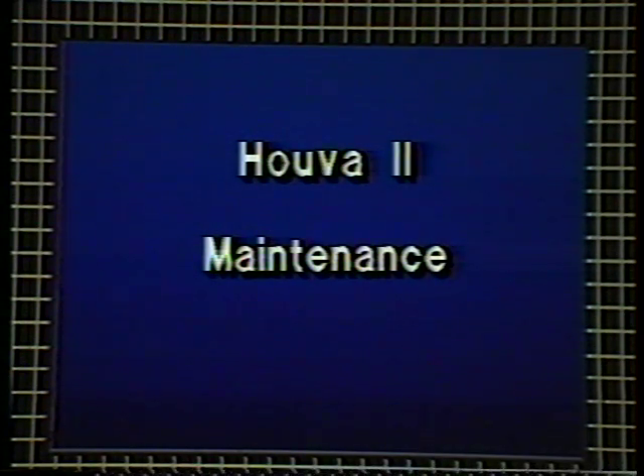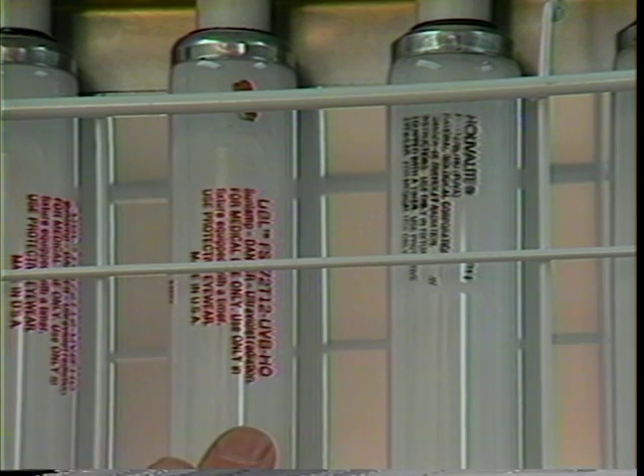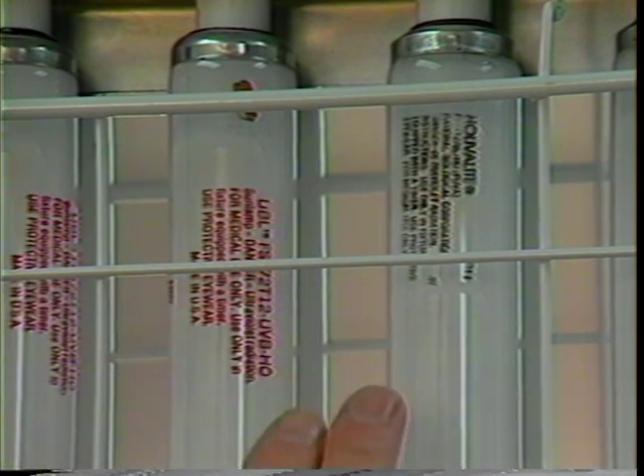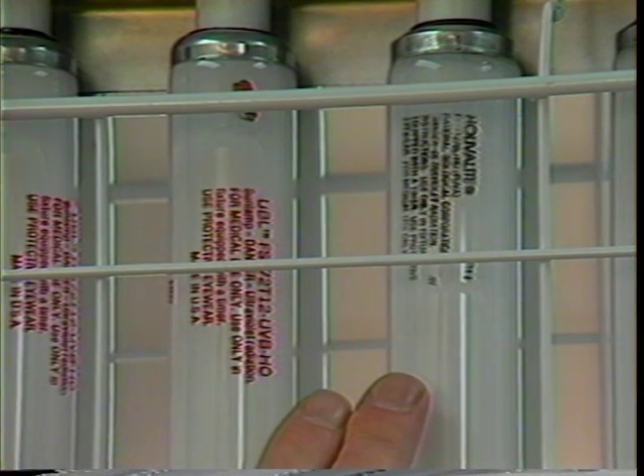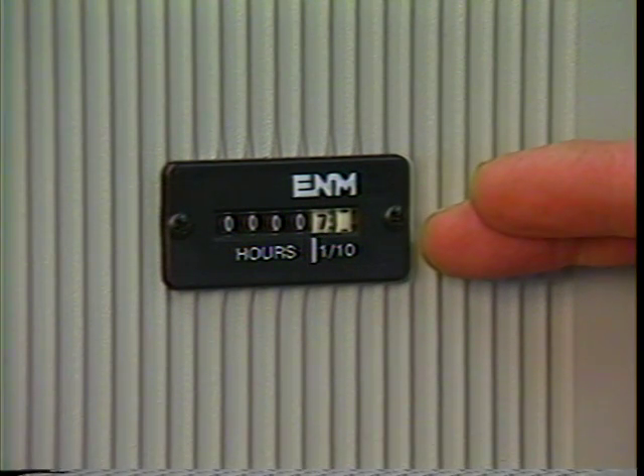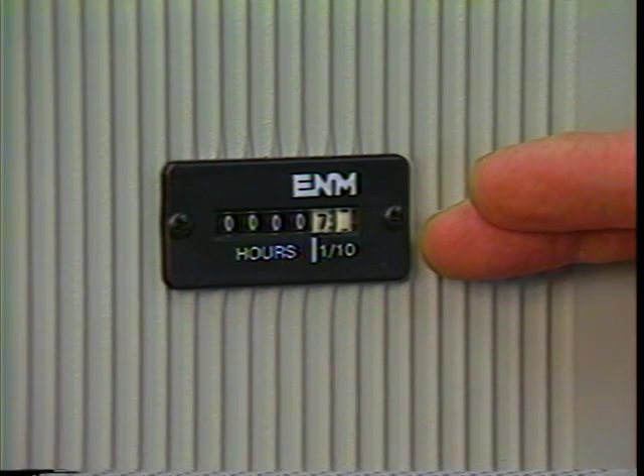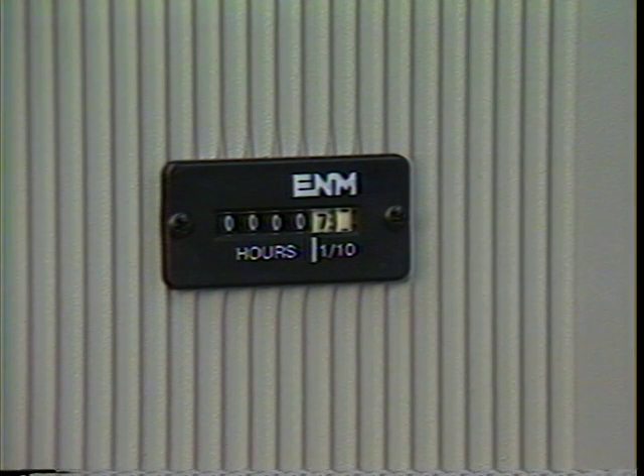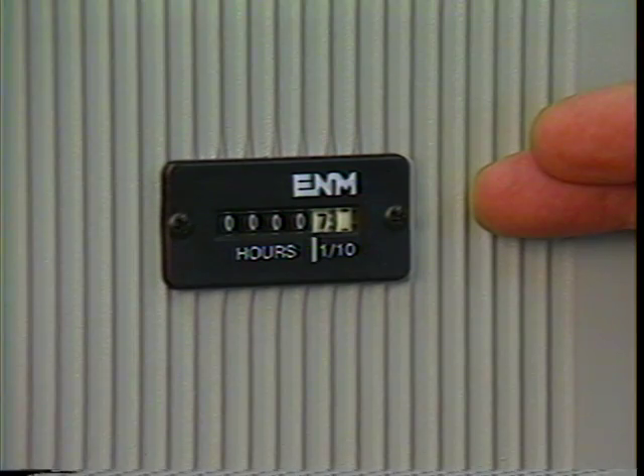The fluorescent lamps in the HOUVA II system, as all fluorescent lamps, have a useful life. The UVA lamps have a 400 to 600 hour effective useful life. The UVB lamps have a 150 to 200 hour effective useful life. Under normal conditions, the number of stops and starts will determine effective useful lamp life. The number of hours of effective useful light is automatically recorded on the cumulative hour meters located just below the PhotoSense timer. If the number of patients is large, it will be necessary to change the lamps more frequently.